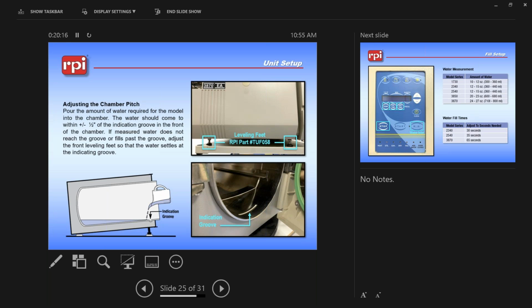Now, when you go to set up a unit for the first time, one of the things you're going to want to do is level out the unit and make sure that the water input is correct. So on the top right picture, you'll see the leveling feet. Those are on every Tuttnauer unit. They're the only ones, the back ones do not level. And then the bottom right-hand picture, that's the fill groove or indication groove for your fill line. Every unit has a specific number of ounces that need to go inside the chamber, which I'll show you on the next slide. What you're going to want to do is grab that set amount of water, pour it into the chamber, and you want to use the leveling feet to get it within plus or minus a half inch of that fill groove.